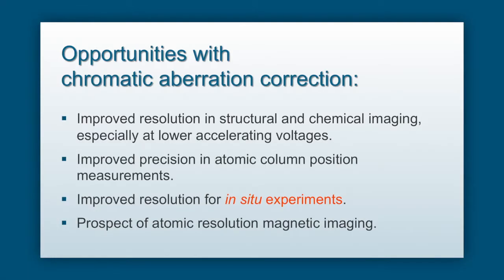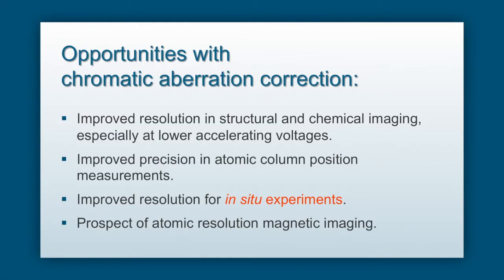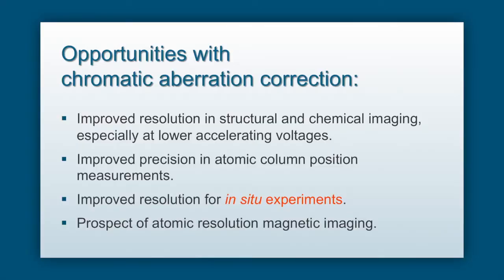Chromatic aberration correction allows us first to improve the spatial resolution of structural and chemical information, and this improvement is greatest at the lower accelerating voltages. Lower accelerating voltages are important because high-energy electrons damage many materials; lower voltages allow us to look at beam-sensitive materials with good spatial resolution. Combined chromatic and spherical aberration correction also provides better precision in atomic column position measurements, with the present generation of instruments offering the possibility of one picometre precision.